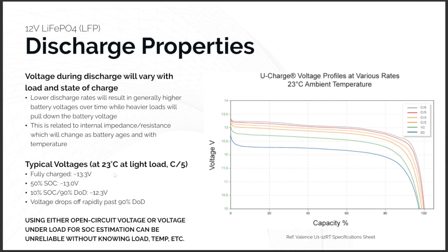You'd have to know your load, your temperature, condition of the battery. So just doing that either open circuit or under-load voltage measurement may not give you a good feel for where you're at, that depth, that state of charge.